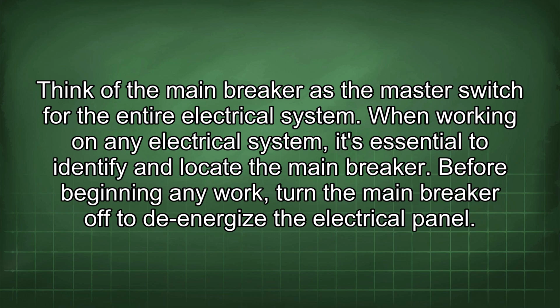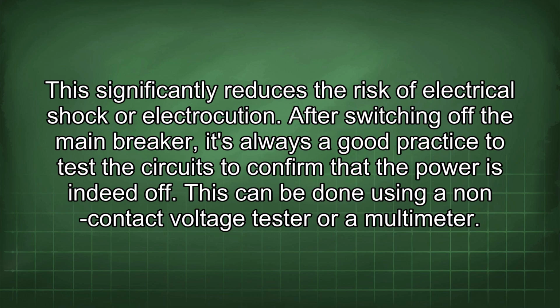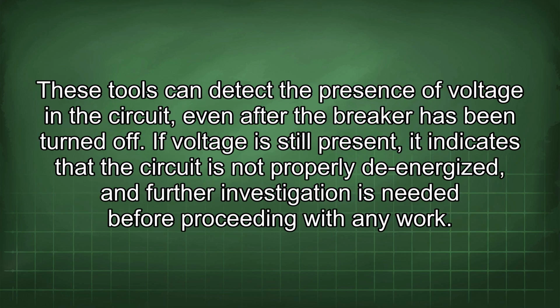When working on any electrical system, it's essential to identify and locate the main breaker. Before beginning any work, turn the main breaker off to de-energize the electrical panel. This significantly reduces the risk of electrical shock or electrocution. After switching off the main breaker, it's always a good practice to test the circuits to confirm that the power is indeed off. This can be done using a non-contact voltage tester or a multimeter. These tools can detect the presence of voltage in the circuit even after the breaker has been turned off.